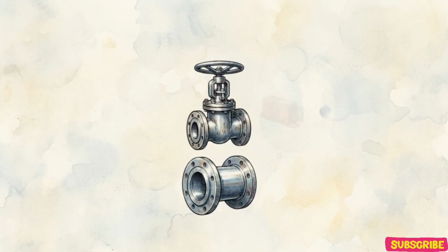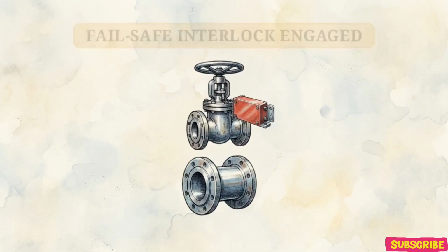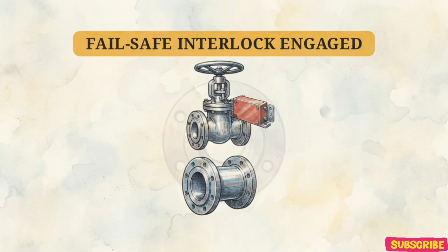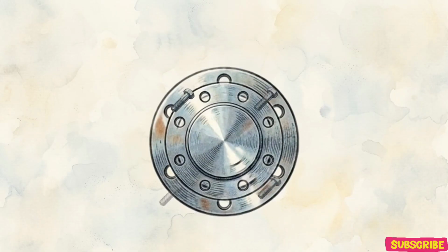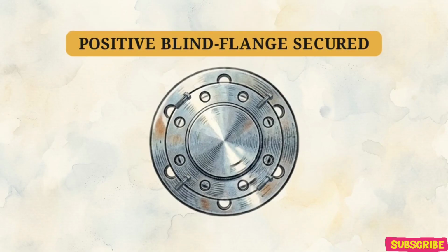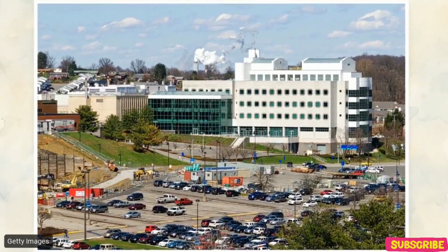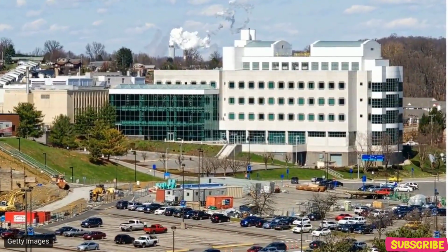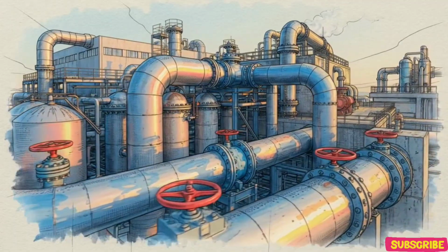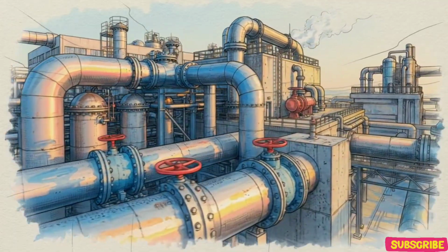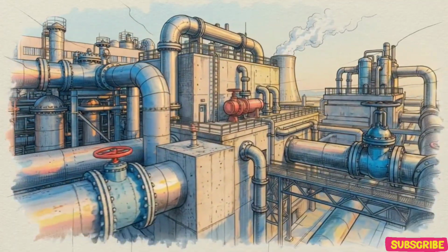To address the initial mechanical failure, industrial codes were updated to require fail-safe mechanical interlocks. Valves can no longer physically open unless positive blind flanges are bolted in place, preventing pneumatic errors from venting a reactor. Finally, the API RP752 mandate was created. Control rooms and administrative buildings must now be blast-resistant concrete structures located far from processing units. The industry updated these engineering standards to ensure that a single pneumatic error can no longer escalate into a supersonic detonation.